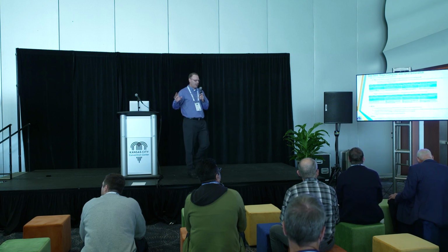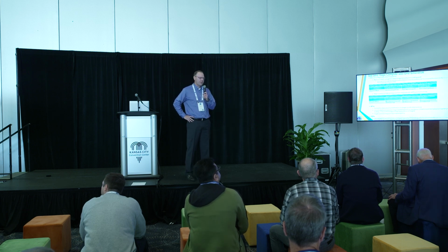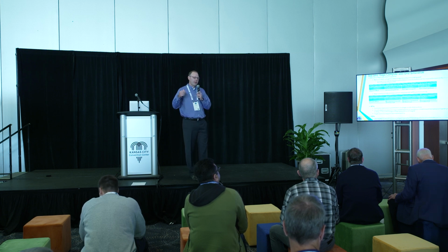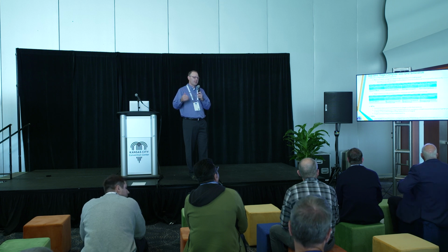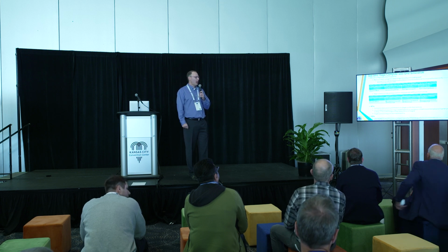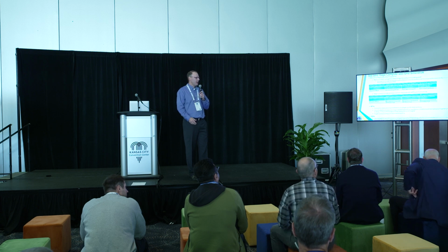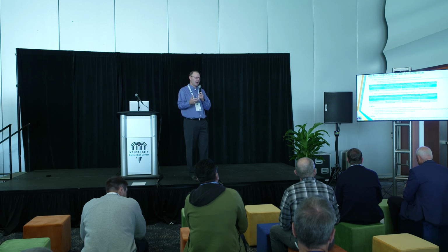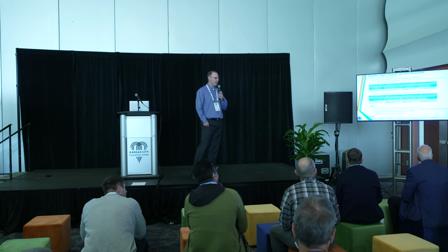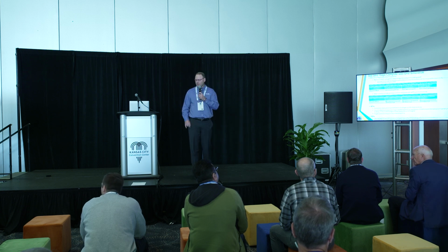So I'm going to next show a grid simulation. This is just to show there are really two major takeaways from the demo. One is the interoperability piece. We're able to get three-phase voltages and provide set points to the legacy devices like cap banks and regulators, and we're also including the energy storage system. The second piece is that we're leveraging peer-to-peer communication with a consensus algorithm to quickly converge to a decision on the optimal voltage set point strategy. In the demo here, we're mainly going to control a cap bank and a battery energy storage system.